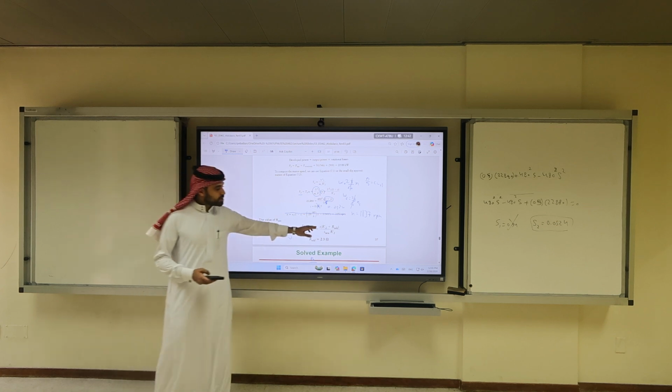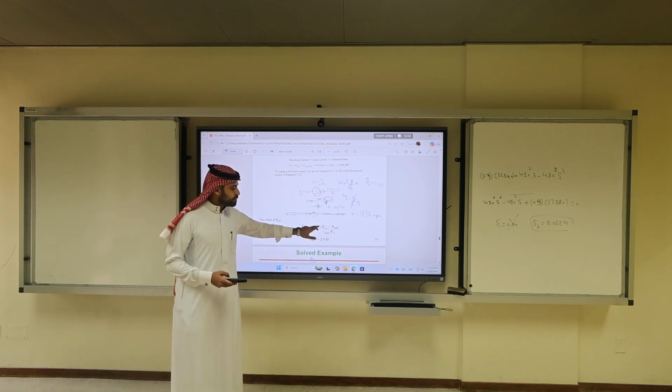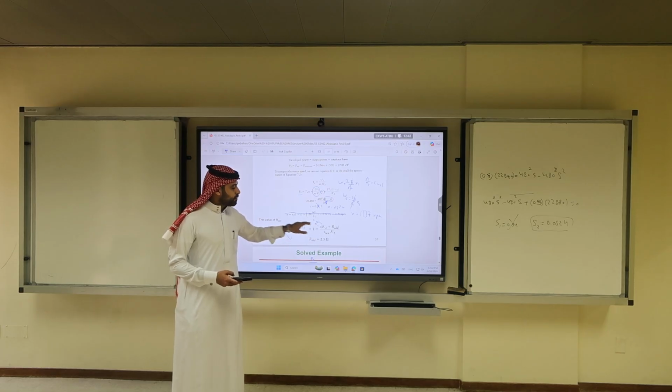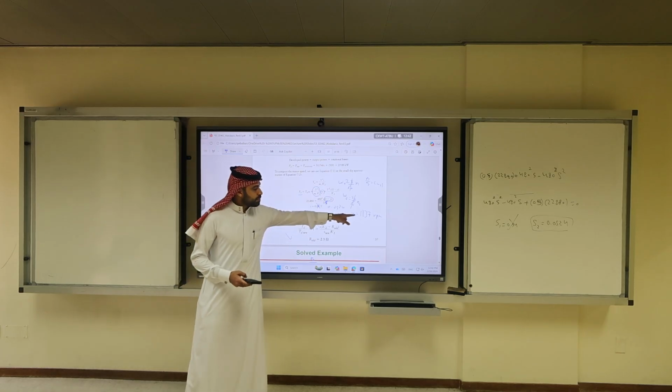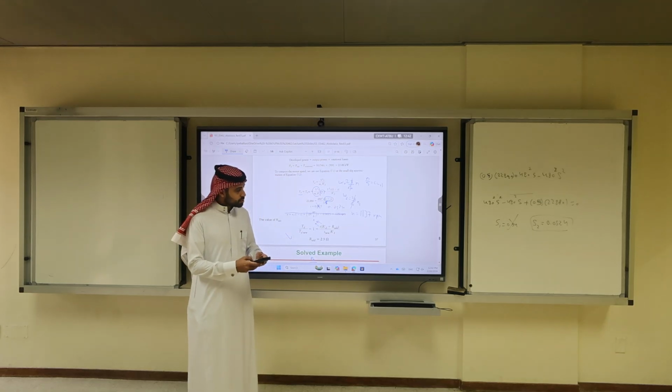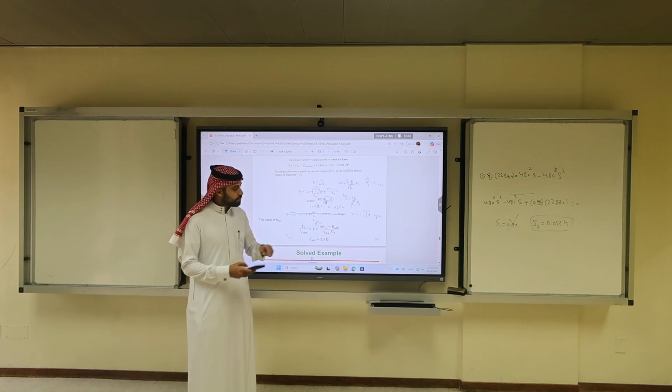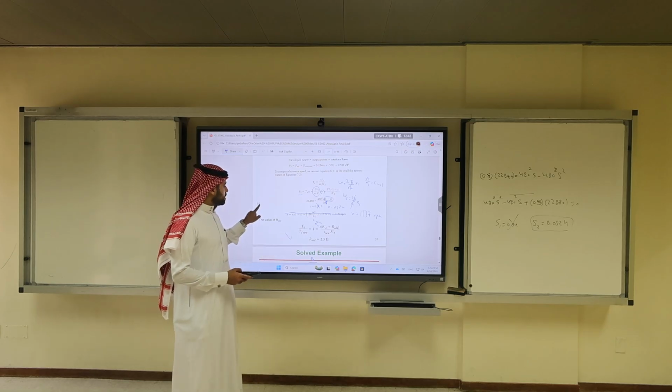Can you do the calculation? What is S? 0.0524. If you reduce the speed by 20%, so 1137 times 0.8, what's the new slip? N new is 909.6.